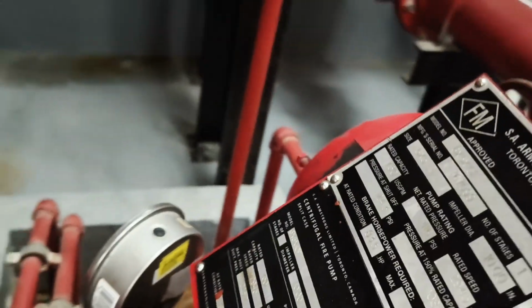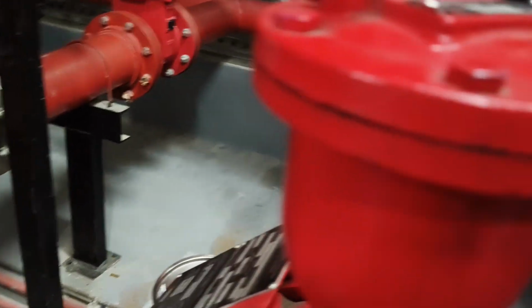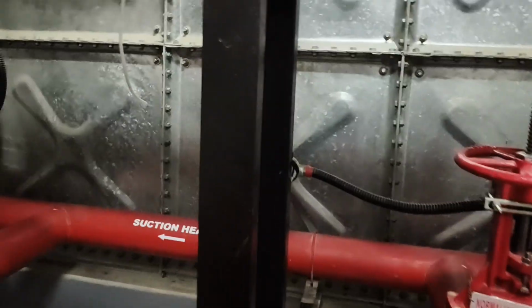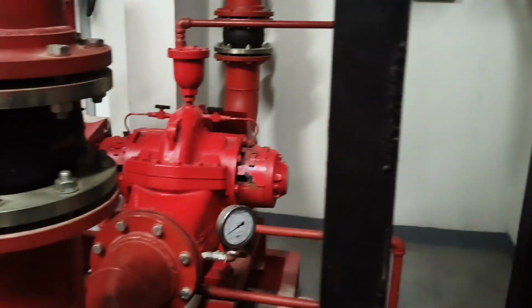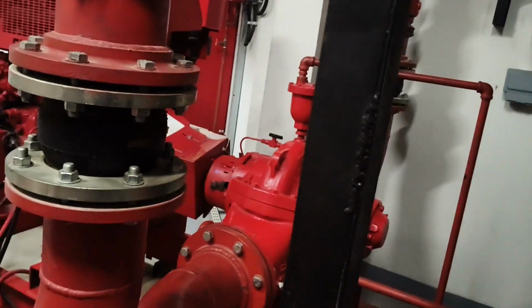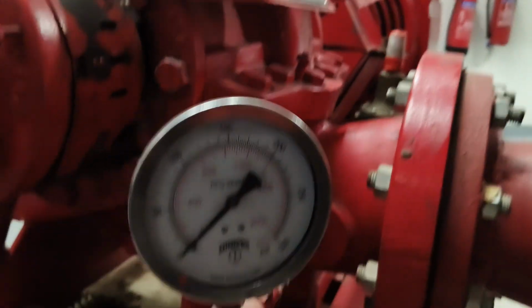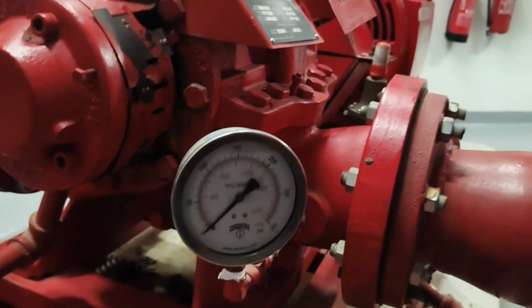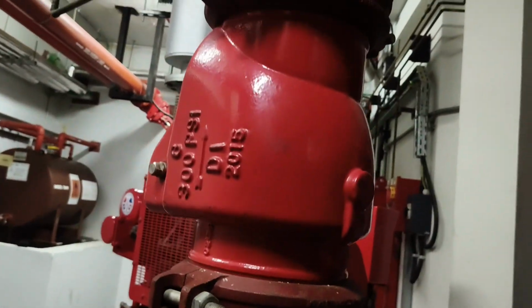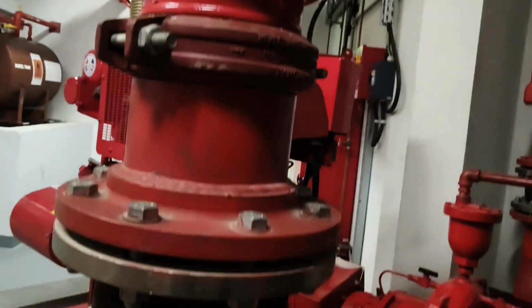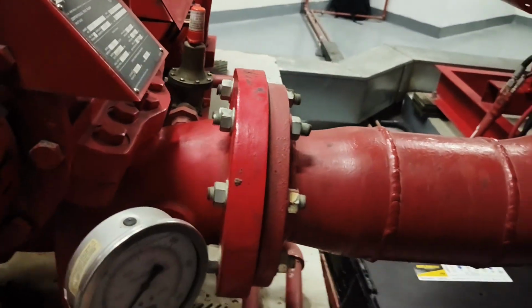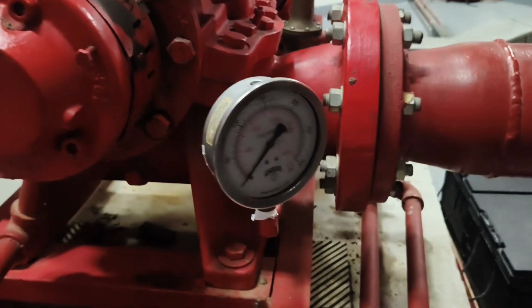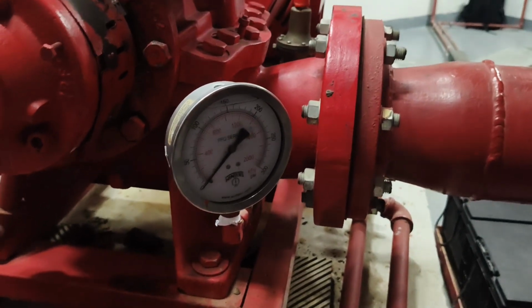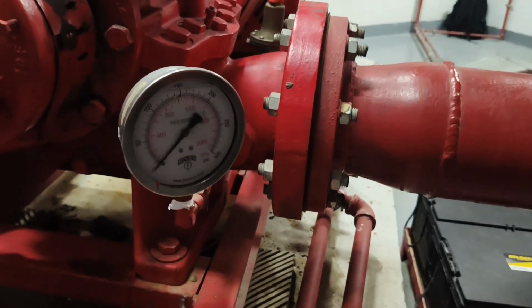And the discharge, we have a discharge pressure gauge that is here. You know, this discharge pressure gauge will always read 0. It works only when it is running. So someone may ask, why is it not working? It's working actually. You could see that there's a check valve here which is holding the pressure inside the system, and from here there is nothing like that. So the water that is here can even be reversed back. So there will be water in the system, but it's not pressurized. It's a normal pressure.